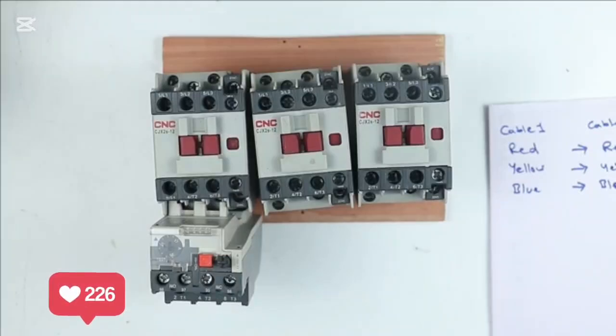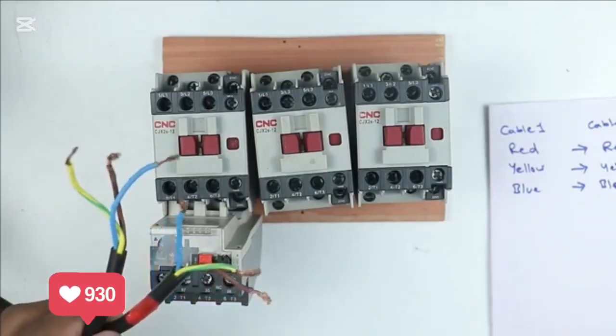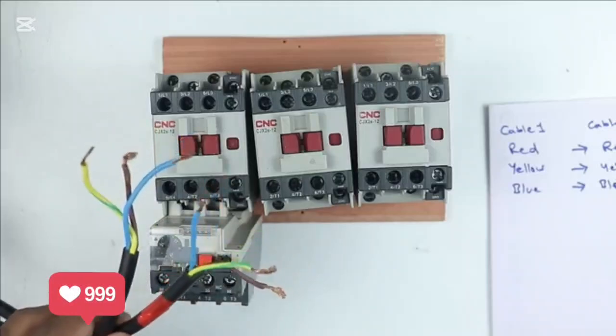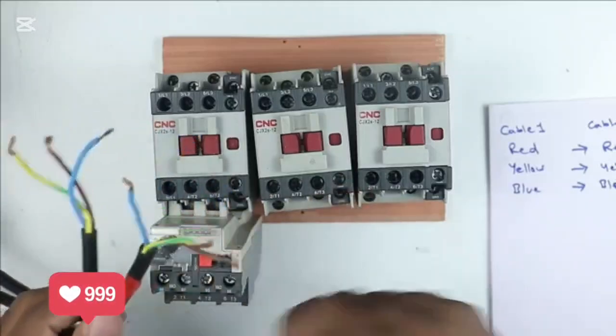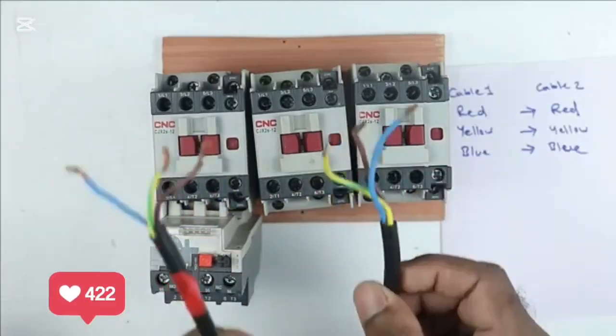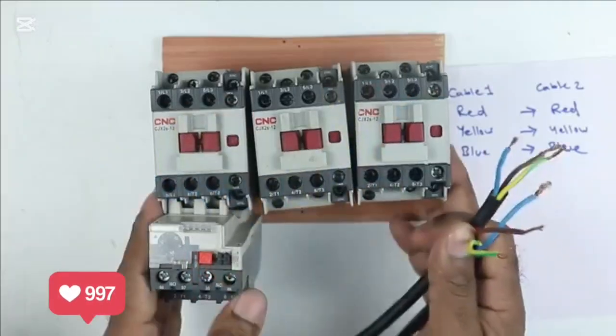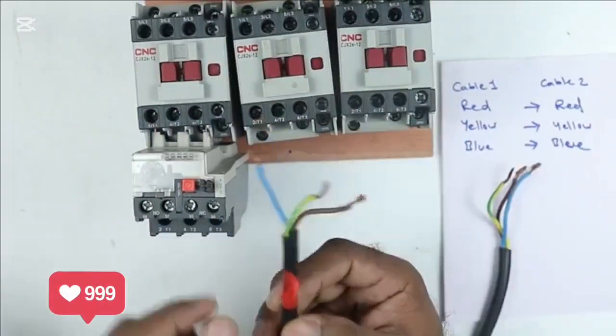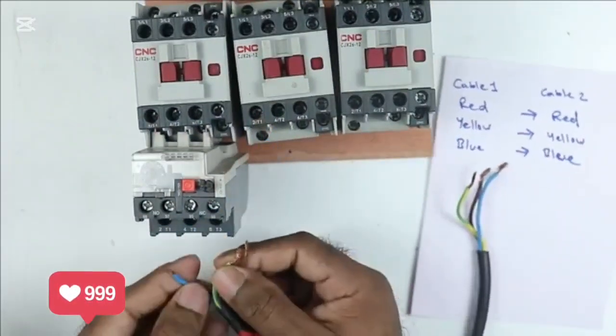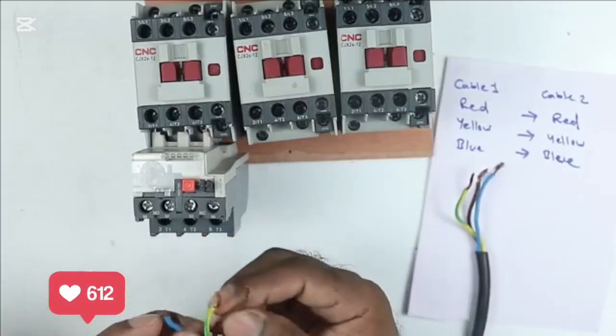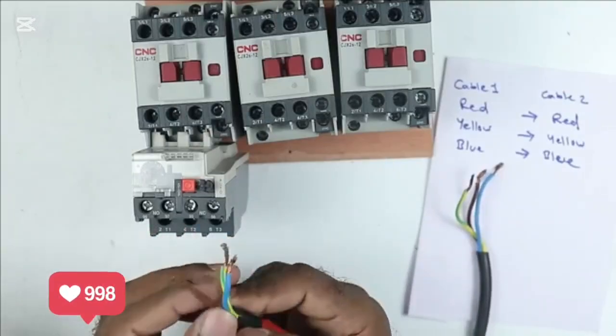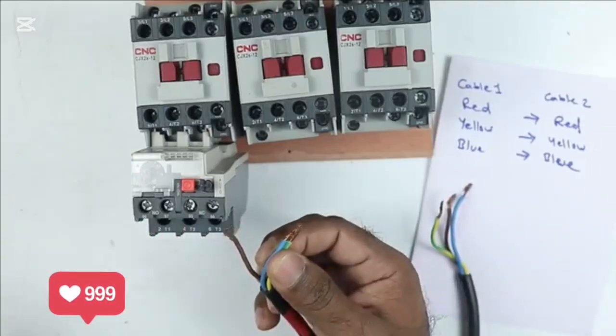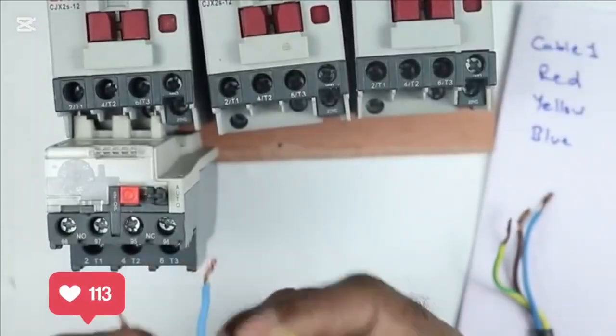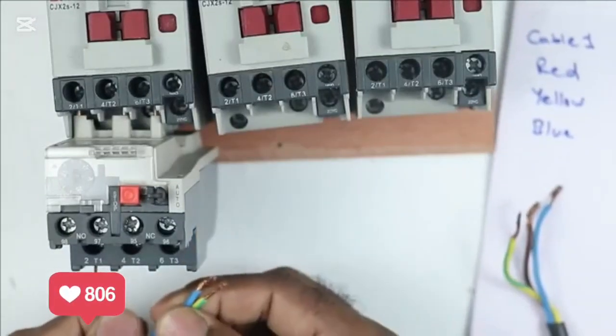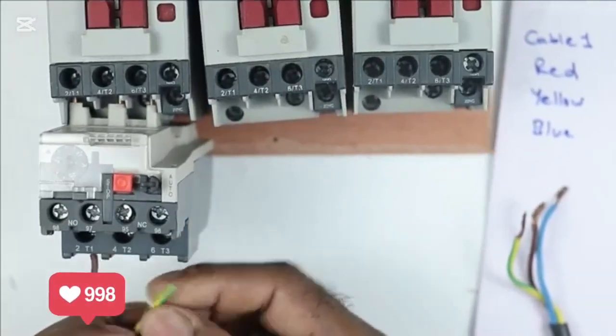Now what you have to do, listen carefully. If the wires are not coming out of the motor from inside, then connect a wire separately by yourself for connection with the starter. Among these two cables, connect any one cable to the output terminal of the overload relay. For now, in cable number 1, I will take all 3 wires and connect them to the output terminal of the overload relay. Okay, before connections, do one thing: keep the phase sequence in mind. Phase sequence means the first wire, I mean the red wire, you have to connect at the first terminal.